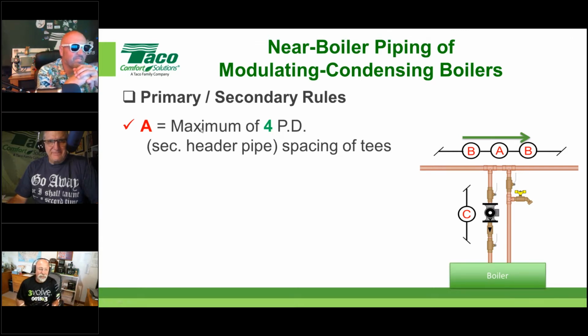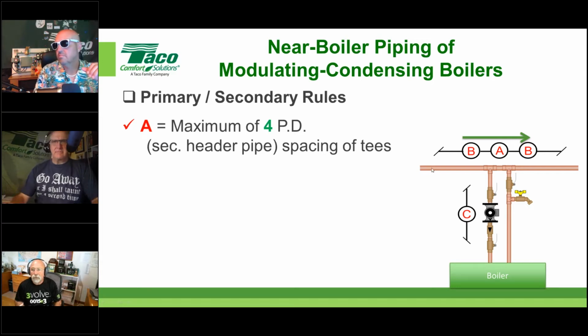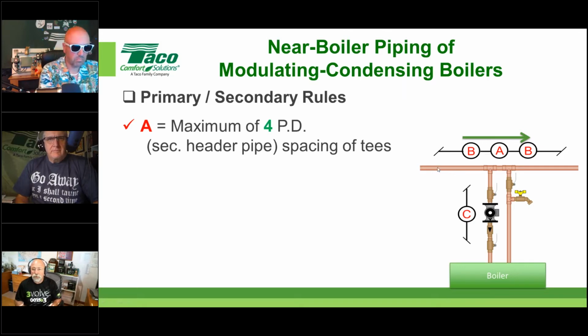In fact, what that means when it says maximum is actually make it closer. So the maximum spacing in between these two T's is 4 pipe diameters of this secondary portion of the system. So if that secondary portion of the system was 2 inch, what's 2 times 4? I better be less than 8 inches there is what the A note means.